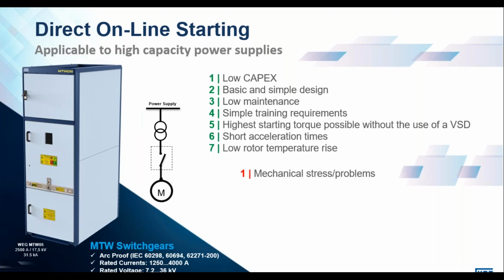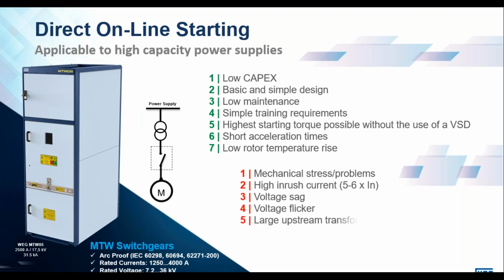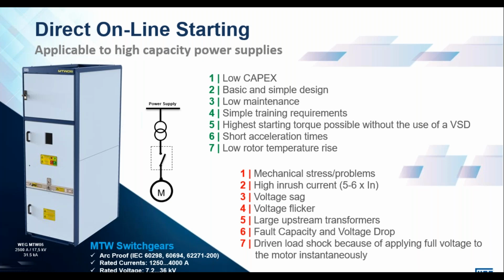Okay. Again, this is something that is common knowledge from an engineering point of view in most cases, but let's just cover the basics. Direct online starting has the following advantages: low capex, basic and simple design, low maintenance, simple training requirements, and the highest starting torque possible without the use of a VSD. I think I need to just put a disclaimer there. Also, you can use a slip ring machine or a wound rotor induction motor with an external rheostat.